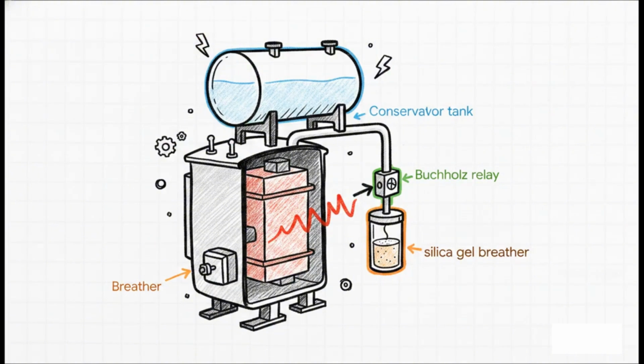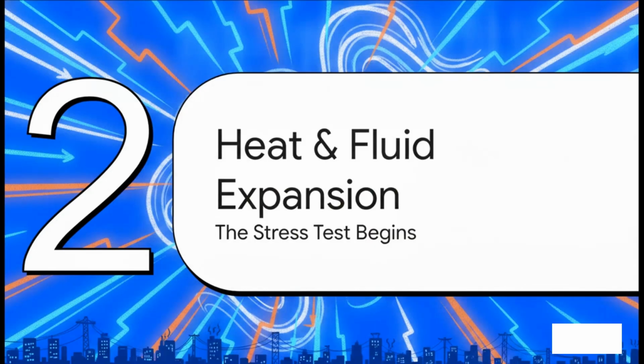Now, before our stress test begins, it really helps to understand the playing field here. Inside the main body, we've got the windings generating the power. Attached to the system is the Buchholz relay, serving as a vital protective device. You've also got the silica gel breather, which acts almost like the transformer's lungs. And finally, the absolute hero of our explainer today, the conservator tank, mounted right up at the top, high above the main tank. Which brings us to heat and fluid expansion.